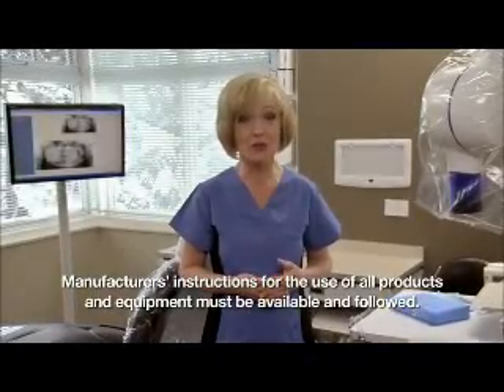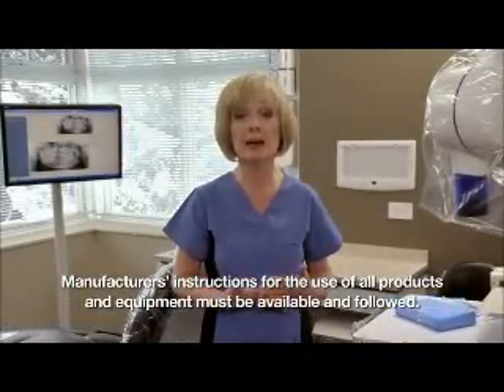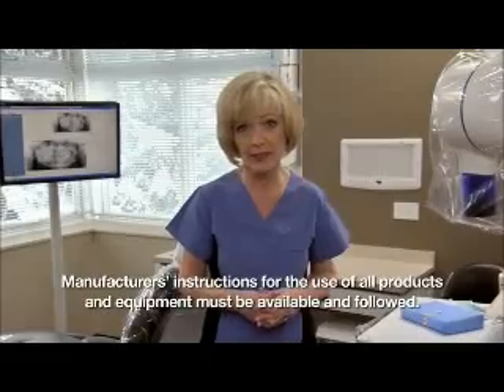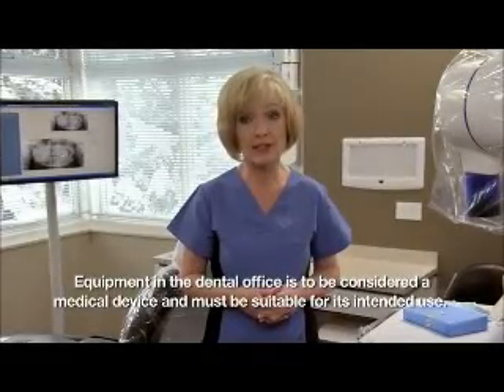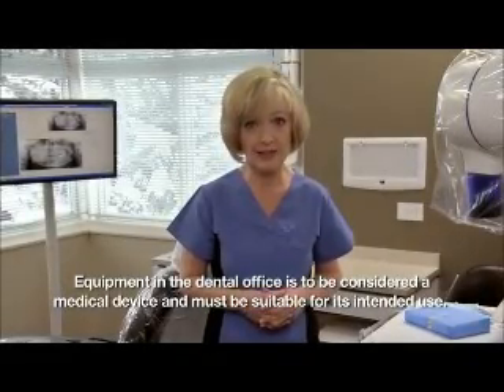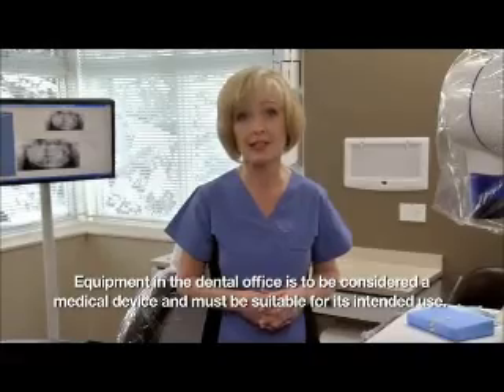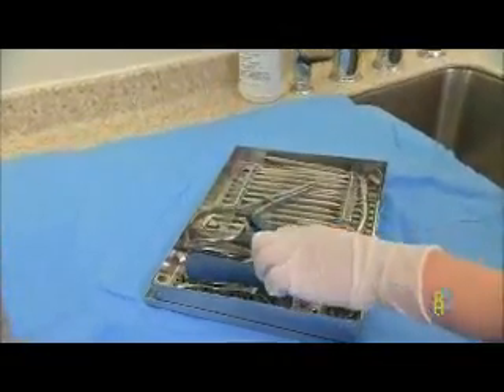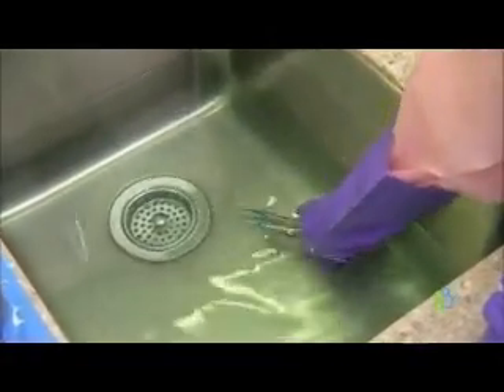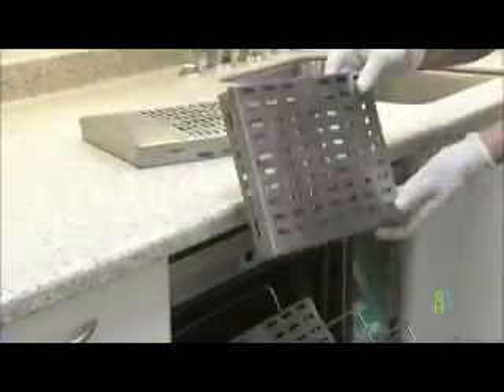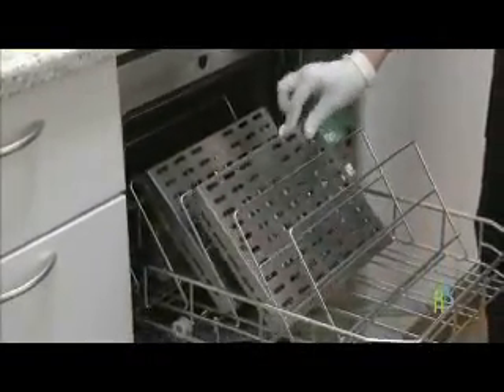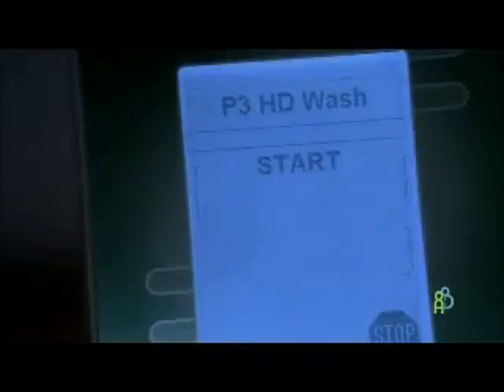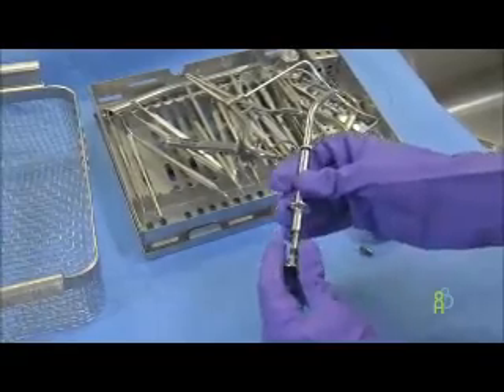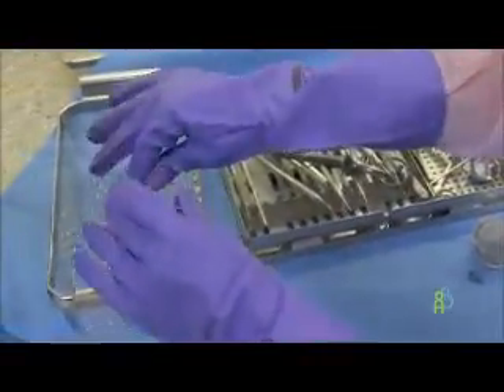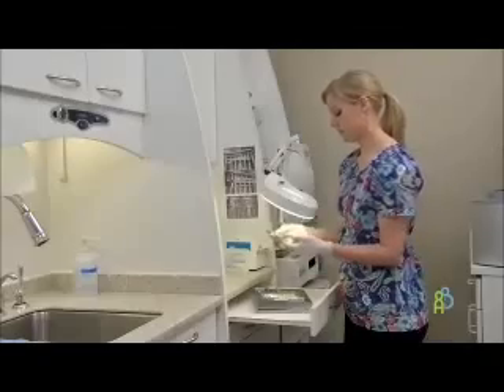Manufacturers' instructions for the use of all products and equipment must be available and followed. Equipment in the dental office is to be considered a medical device and must be suitable for its intended use. Meticulous cleaning is the first and most important step in reprocessing. Cleaning always precedes disinfection or sterilization. The cleaning process includes sorting and disassembly of dirty devices, washing, rinsing, drying, and inspection.